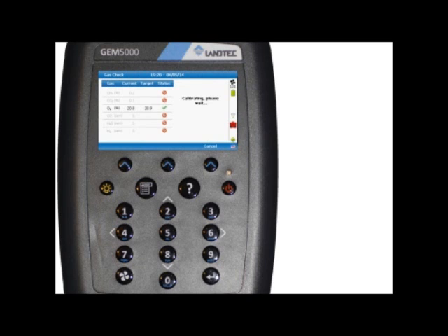The unit is now calibrating. A calibration successful message will appear indicating all channels have been properly calibrated. In this case, it's just this O2 channel that is being calibrated, and as you can see, it has a green check mark. Note that at this point the values have not been stored to the memory, so do not turn off the pump until the calibration values have been stored. To save the results, press the right soft key to select exit. Now the results are saved. At this point, press the right soft key to exit, and this will automatically turn off the pump.